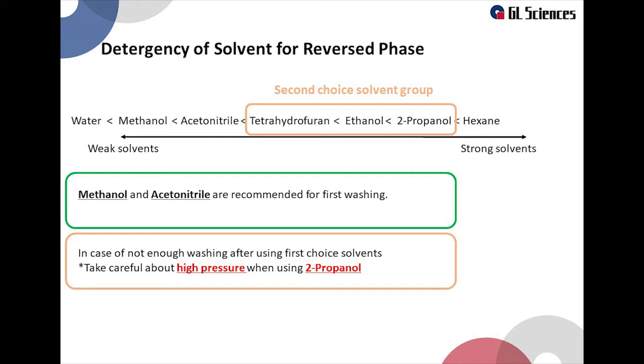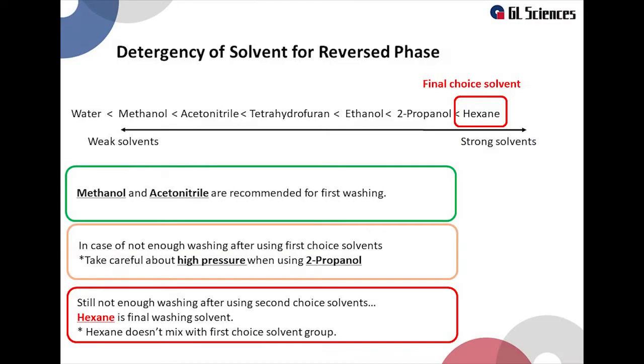However, take care about high pressure when using isopropanol. If the cleaning is also insufficient with the second choice solvent group, use hexane as the final choice solvent. However, hexane does not mix with the first choice solvent group. Therefore, make sure to use hexane after applying the second solvent group. We will explain the washing method on the following slides.